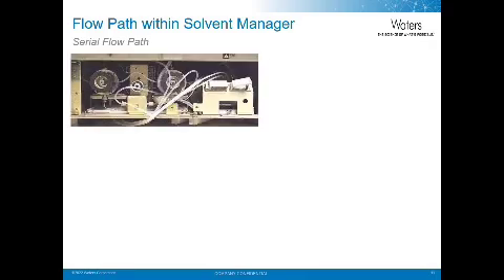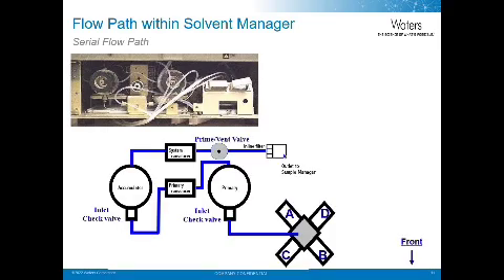So after the mobile phase is degassed, it goes through the rest of the solvent manager, which has a serial flow path design. Here we have a picture of the actual solvent manager. The degasser tray mentioned in the last slide is shown here. This is just a front view. If we look at the path itself, the mobile phase goes from the degasser to the GPV valve. The valve then proportions the mobile phase determined by the method and parameters, then flows to an inlet check valve, into the primary pump head, then through the transducer, another check valve to the accumulator, through the system transducer, and then through the prime and vent valve, then onto the inline filter and to the sample manager.